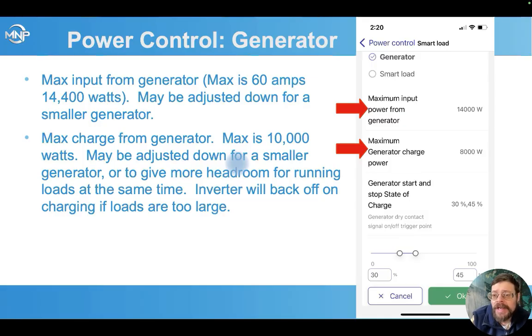Going through what you'll actually see in the app when setting up this programming. So this is when you go to Power Control, Smart Load, set it to Generator. Remember to dark start the inverter by shutting it down completely, shutting off the battery breaker for a minute, and then turning the battery breaker back on. And then you can go through these programming steps. You'll set the maximum power input from the generator, maximum charging power to batteries from the generator, and your start and stop state of charge.